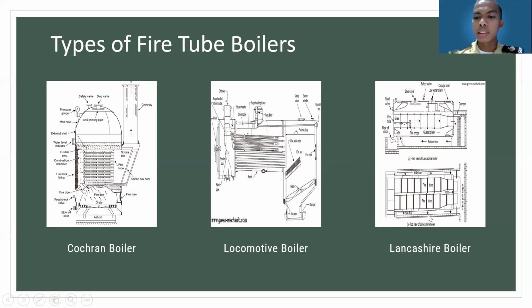And this is the Lancashire boiler. So the Lancashire boiler is a horizontal type and internally fired boiler, as the furnace is located inside the boiler. So it is a natural circulation boiler and generates low pressure steam. The thermal efficiency is high, about 80% to 90%. The size of the boiler is roughly 7 to 9 meters in length and 2 to 3 meters in diameter.